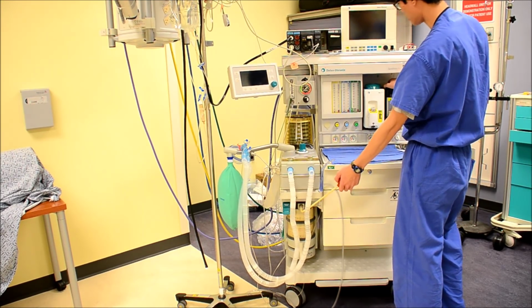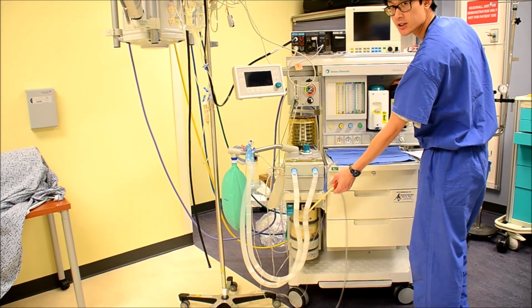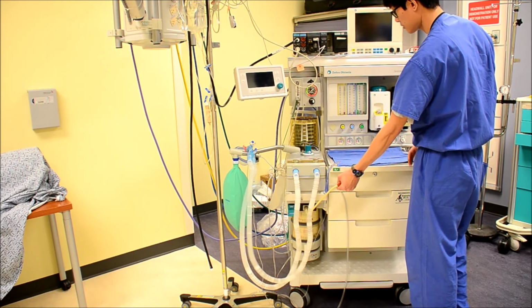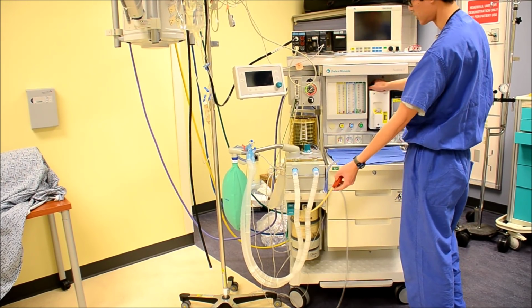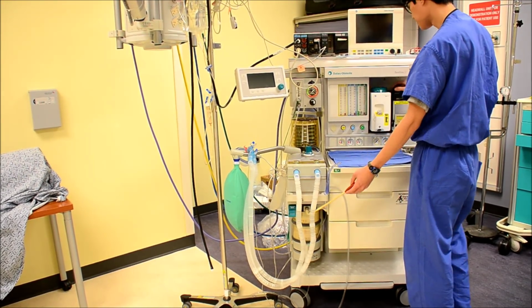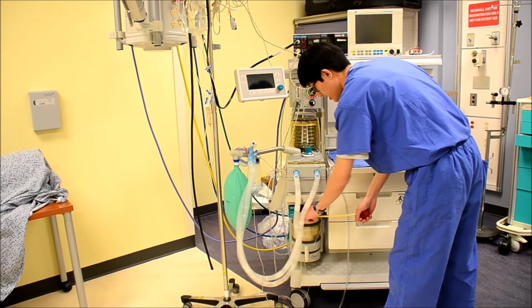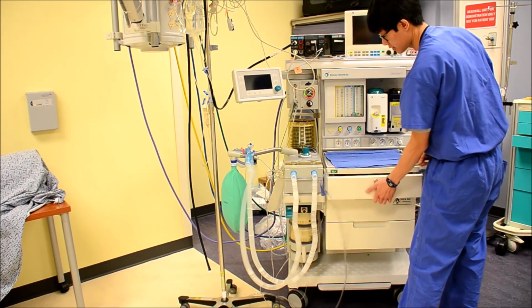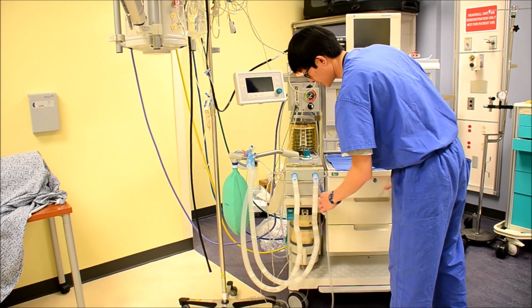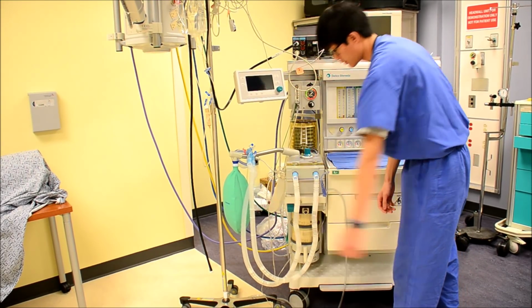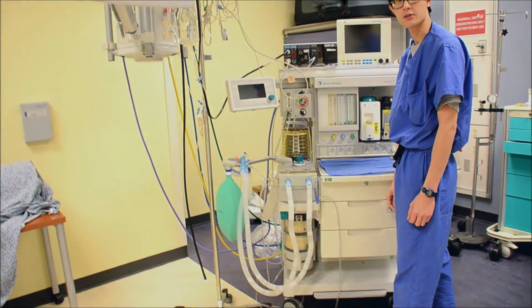We'll go ahead and close that one. Open up your other vaporizer, squeeze your bulb and let it hold for 10 seconds, and check the interlock system for the other side. Once we're done with that, we can disconnect your bulb section. You can put that away, and make sure you go ahead and close off your common gas outlet lever.